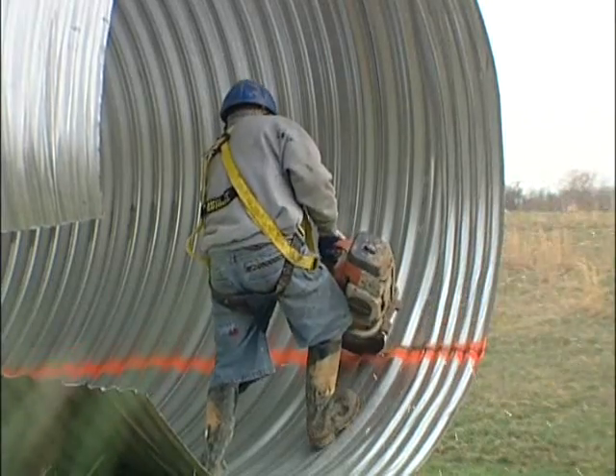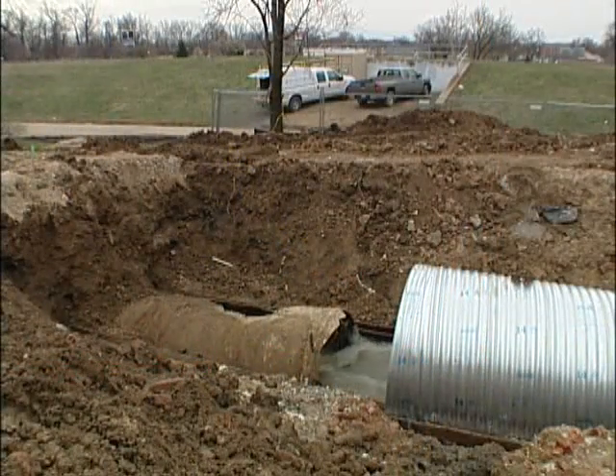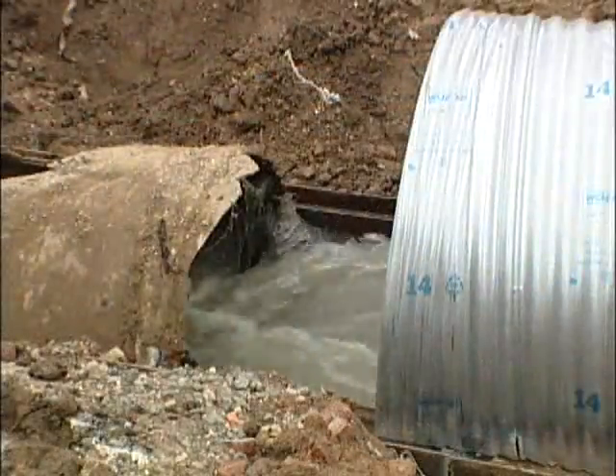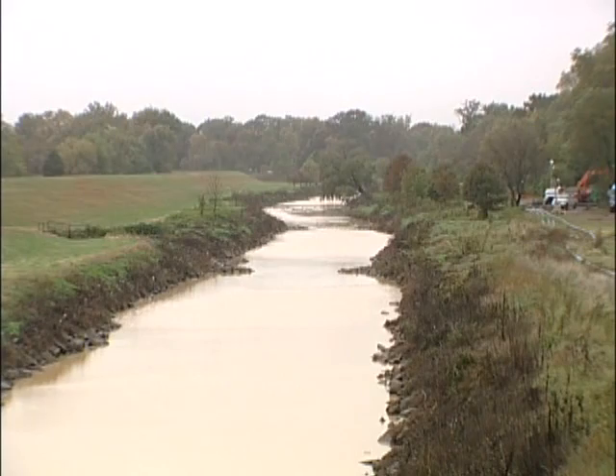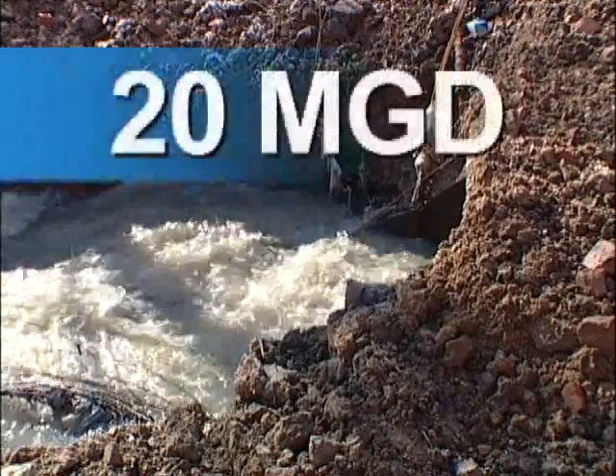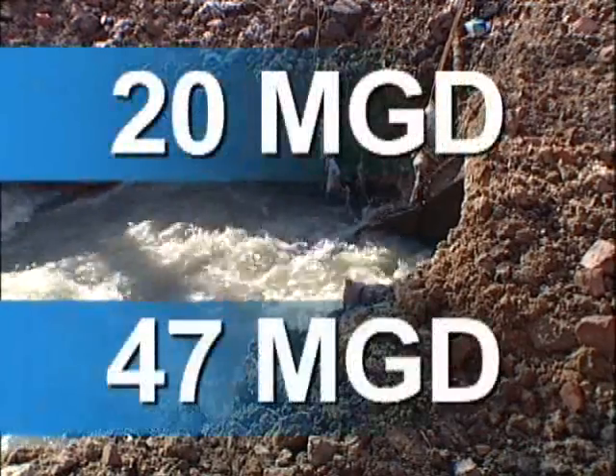This is a classic example of what happens if you don't have the resources to have a proper maintenance program. In plotting a plan of attack, shoring up the area around the broken section of PCCP was paramount — if this broke loose and overflowed, you're talking a catastrophic event. We're about 300 feet away from the northwest branch, with average flow ranging from 20 million gallons on the low end to 47 million on the high end.